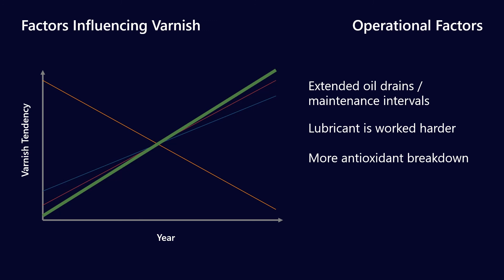Finally, extended oil drains and maintenance intervals mean we're asking the lubricant to last longer — it gets worked harder, leading to more breakdown of the antioxidant package. When you put all these factors together, yes, the industry has moved from Group I to Group III base stocks, improving oxidation stability. But there are so many more factors acting against us: reduced solubility, changes in how gas turbines are operated, and increasing turbine operating temperatures. That's why, even though lubricant technology has improved substantially over the last 40 years, we're actually seeing more turbine varnish problems in 2020 than we probably were back in the 1980s.